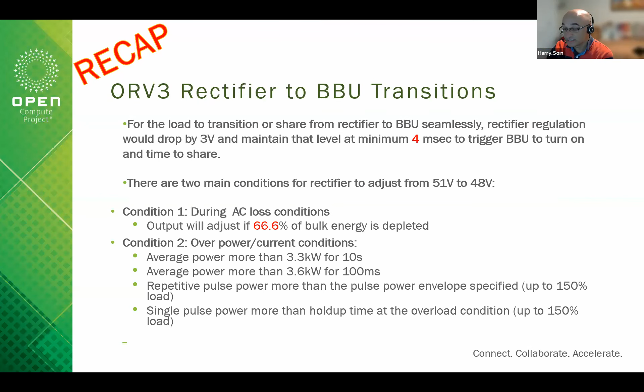These are peak shaving conditions, overpower conditions, with an envelope for repetitive peak pulse power up to 150% of the load - that hasn't changed. However, we looked at single pulse power that was more than hold up time for overload conditions - that's the area we tried to change and adjust. So here's an example.